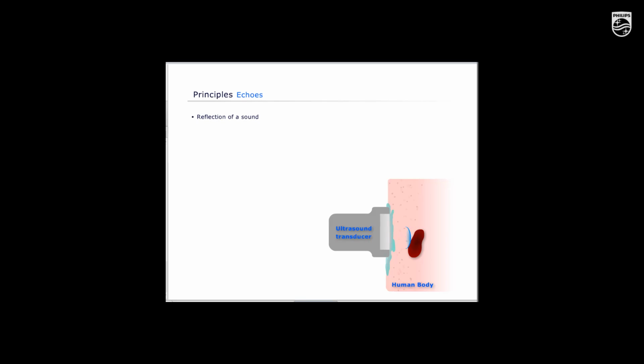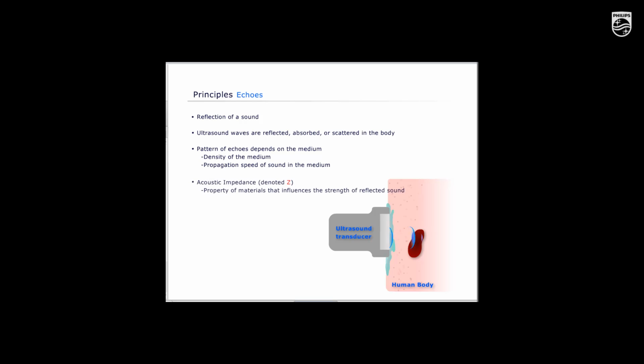An echo can be defined as the reflection of a sound. The reflected and scattered sound waves produce a pattern of echoes that is necessary for ultrasound imaging. This pattern of the echoes depends on the characteristics of the medium, such as the density of the medium and the propagation speed of the sound in that particular medium. There is one property that will help us understand how the sound interacts with the medium. It is called acoustic impedance. Acoustic impedance describes the relationship between acoustic pressure and the particle vibrations in a sound wave. You will find that impedance increases if the density is increased or if the propagation speed is increased.